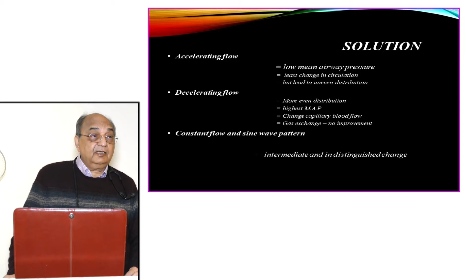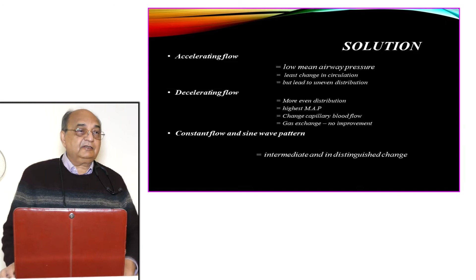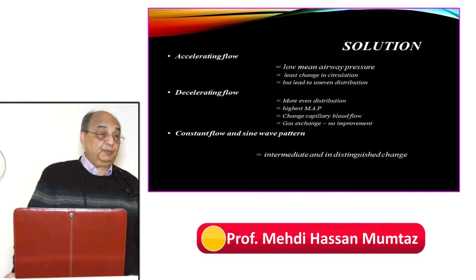You have a provision in some ventilators to have different types of flow, accelerating and decelerating. If you're using decelerating, it means you give flow quickly and then gradually reduce the flow. You will have a more even distribution with this, but there will be the highest mean airway pressure, because when you put the gases with a high flow into the lung, it will create pressure. So we'll have a mean airway pressure greater than what we get with the accelerating flow. And there will be a change in the capillary blood flow. If you increase the flow into the lung quickly, the bigger vessels will dilate, the smaller vessels will be elongated, and that will create resistance to flow. So pulmonary hypertension will be induced in those patients. That's not a good thing.